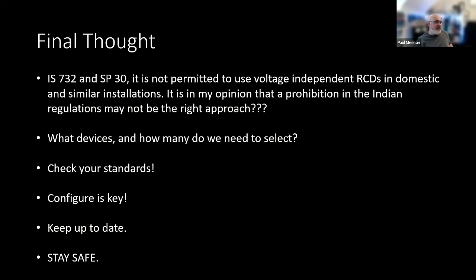Indian Standard 732 and SP30, it is not permitted to use voltage-independent RCDs in domestic and similar installations. However, in my opinion, and I'm sure Chris will agree, the prohibition in the Indian regulations may not be the right approach. Maybe there's a little bit more work needs to be done there. We also need to think, what devices in relation to the earthing do we need, and how many do we need to select? We need to check our standards.